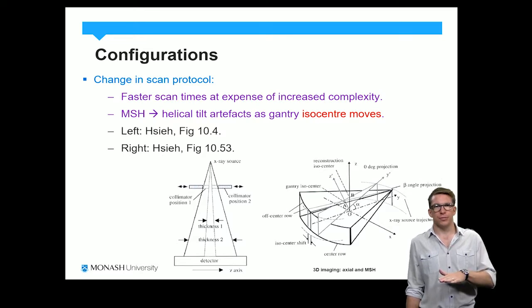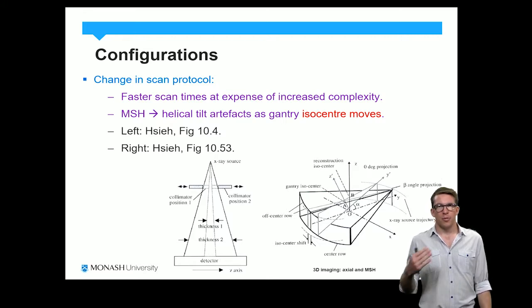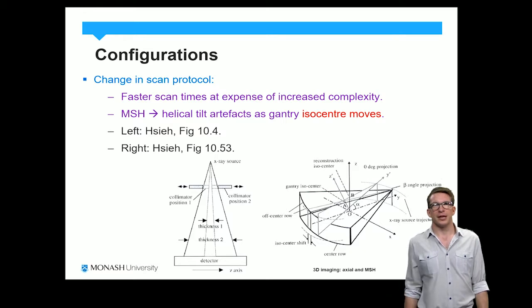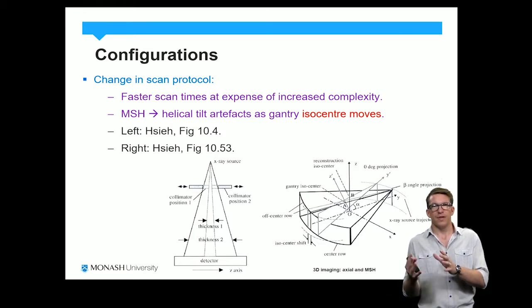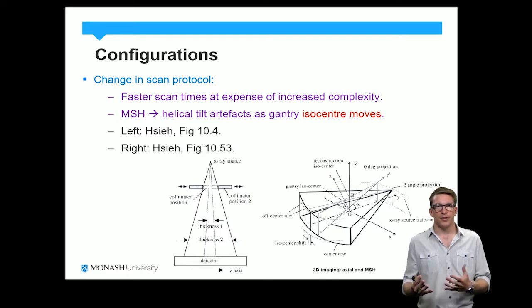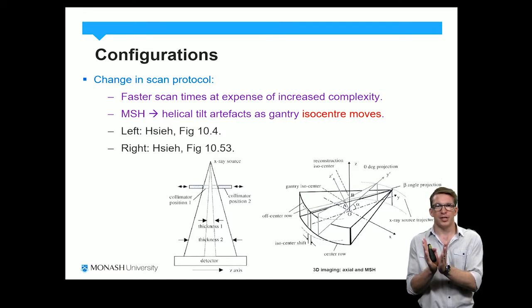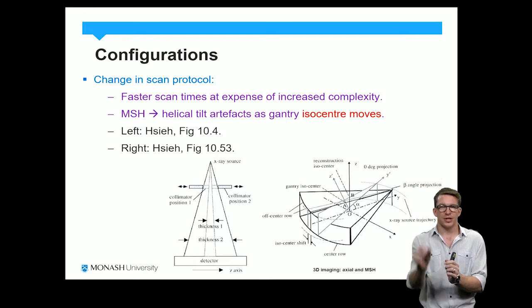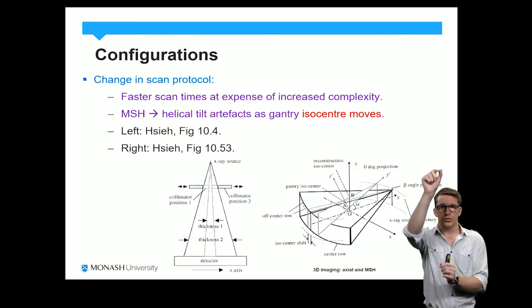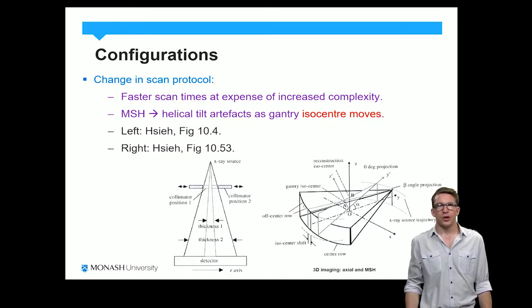If we're going to use gantry tilt to avoid scanning the eyes, the problem with multi-slice helical scanning over single-slice helical scanning is that we have this variability in the isocenter. The isocenter plays a very important role in terms of all of our quantities being defined at the isocenter of the scanner. We have a divergent beam, and by its nature a divergent beam means there is a degree of magnification, so the size of things varies as we move with increasing distance from the source towards the detector. It's important that we account for this in our reconstruction process.